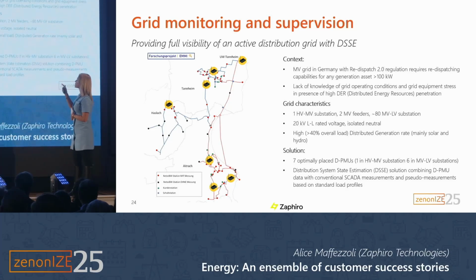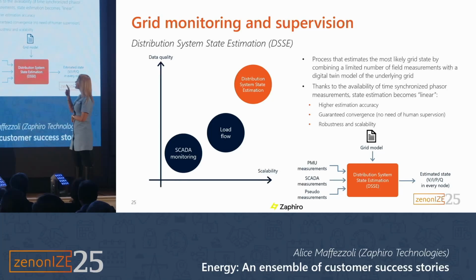So our solution was to deploy 1 PMU in the primary substation and 6 PMUs in some selected critical points in the secondary substations. So with a total of 7 PMUs, with a coverage that is less than 10%, we could provide visibility in all the grid, thanks to the distribution system state estimation. That is the module that enables the observability of the status of voltage, current, power, so active power and reactive power.